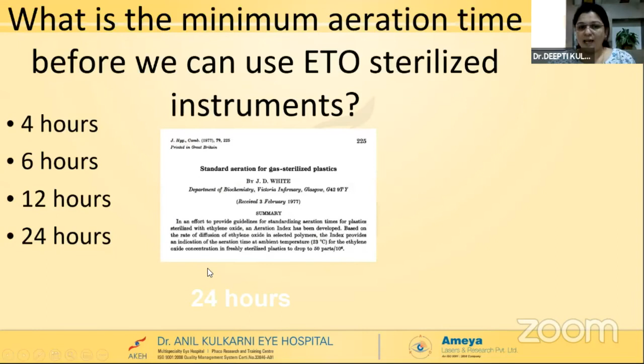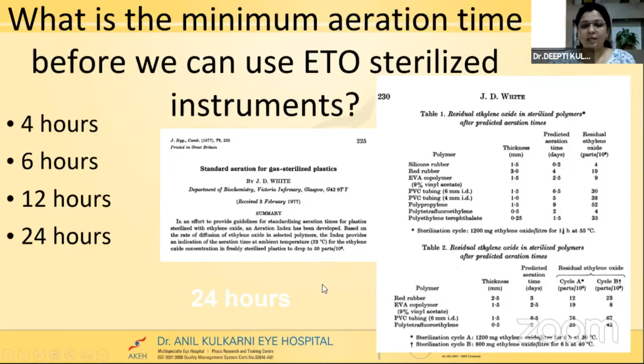There have been various studies where, first of all, the concentration that we must achieve is 50 parts. And for this concentration to be achieved, it takes on average 1 to 5 days. So the safest bet is to go for at least 72 hours, especially for those instruments with a lumen, where we are going to reuse it. But the minimum requirement is 24 hours.